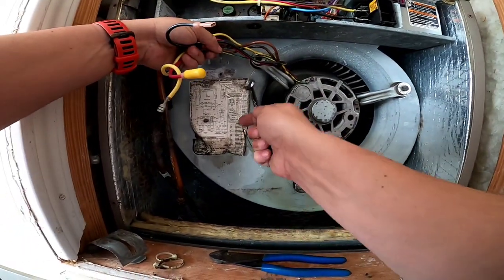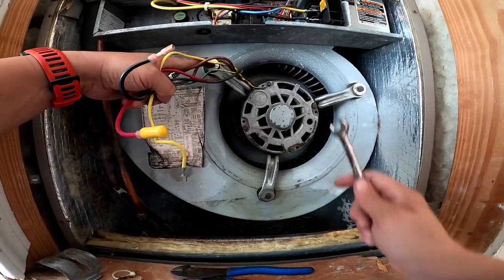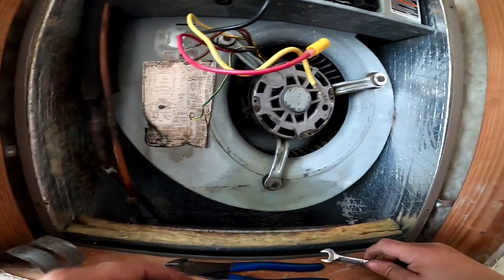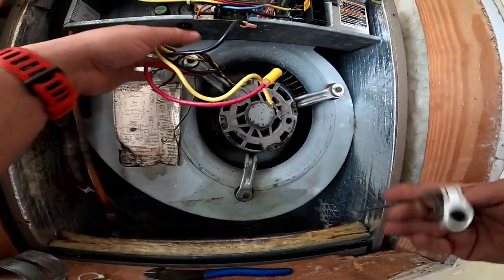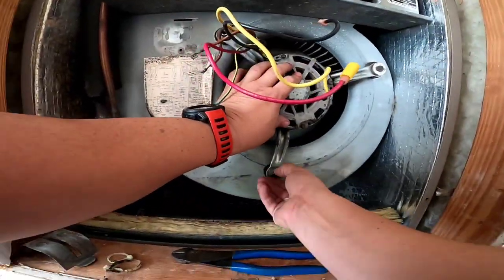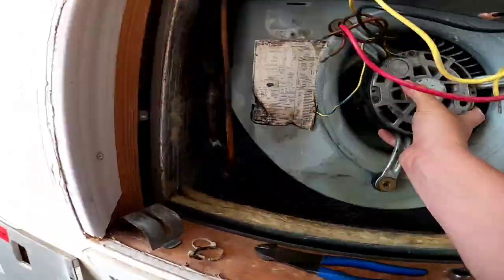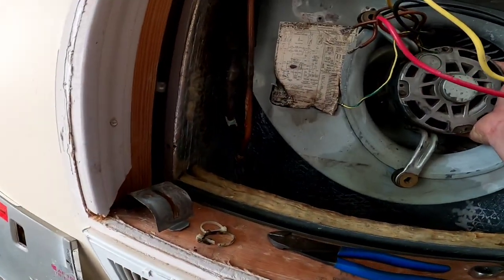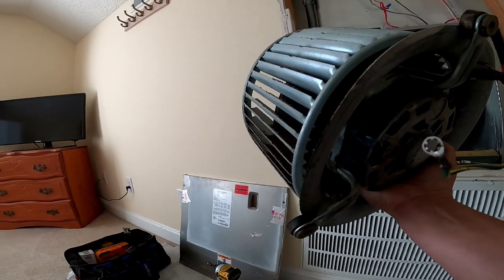As you can see, this ring goes all the way around, so all you do is take out these motor mount bolts and the blower, this ring, and the wheel will all come out — so you don't have to actually take the housing out. Makes it pretty convenient. One thing comes out just like that.